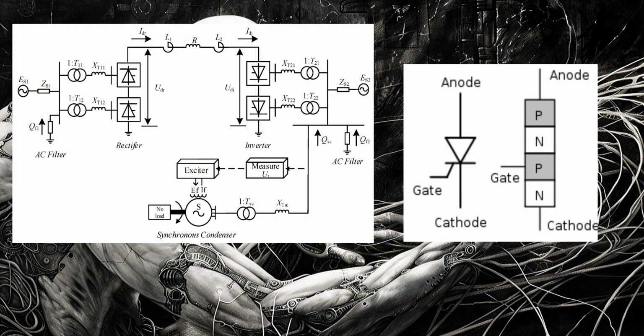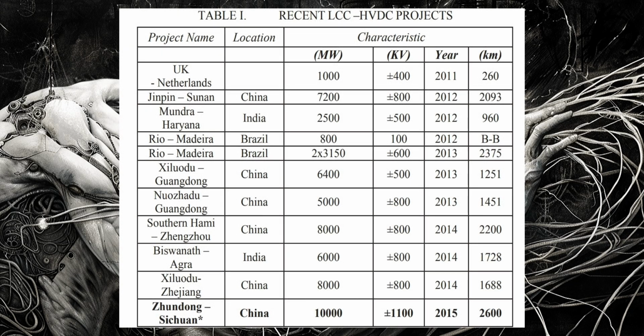LCC achieves its control by regulating the firing angle alpha on both the rectifier and inverting side. It has an approach that utilizes a unidirectional line commutated flow of DC current, which is injected into a receiving AC network. Power reversal from one station to another is carried out by inverting the DC voltage polarity in both stations, but the current direction remains constant. The technology operates with good reliability and minimal maintenance. It's the most suitable way of transmitting bulk power using high-voltage transmission lines.